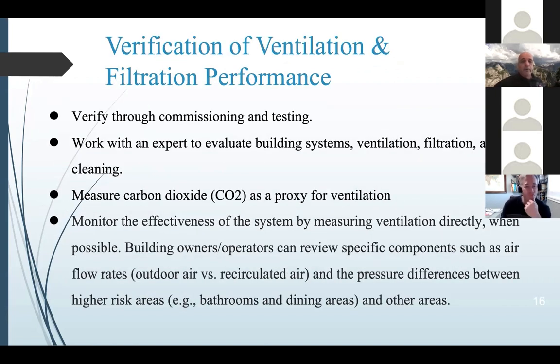So one of the ways we're doing it at some of the schools, which is recommended by UC Davis and the Energy Commission, is to verify through a commissioning agent or a testing company that your system functions as it was designed. Most systems that are installed, especially in commercial buildings, that go through the permit process, all have to meet Title 24 requirements, and Title 24 requires all buildings to vent. Green buildings typically vent more than regular buildings. But if it's a building built through the permit process, when it was built, it did have a ventilation design. And you want to be able to go through it and validate that it's working as it was designed. And one of the other ways we do is we also monitor CO2. And CO2 helps us validate the performance of that equipment. If we're seeing high CO2 levels in the building, we know it's not venting like it's supposed to. So CO2 has become kind of the canary in the coal mine, as I mentioned, as a way to validate that your building is being ventilated properly.